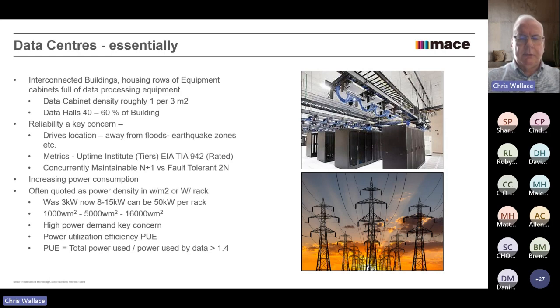There was a guy, I think it's Christian Belady, I think his name is, from Microsoft. He coined the term power utilization efficiency, or PUE, and this was really to try and make the data center business a bit more efficient. This was a ratio of the total power used in the data center divided by the power used for just driving the computers. So if you have a 10 megawatt data center, meaning 10 megawatts of data power, but it's actually using, say, 15 megawatts of power at the incoming supply from the grid, that would have a 1.5 PUE.